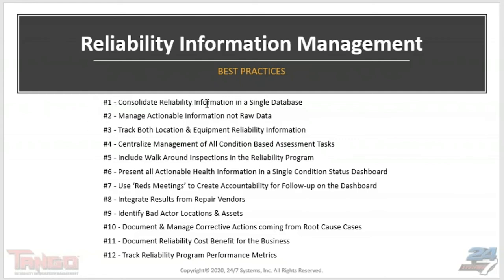Best practice number one: use a web-hosted, or cloud, database. This makes it accessible to people inside the plant who are the dominant users, and by using today's cloud technology, significant security levels can provide portals for outside vendors — service contractors doing vibration analysis, thermography, oil analysis labs, or repair vendors like motor shops — to input information directly, skipping the emailing process that ends with info never becoming searchable database content.